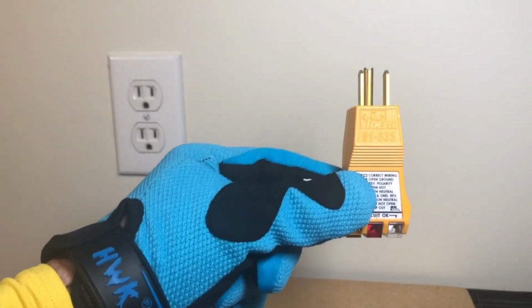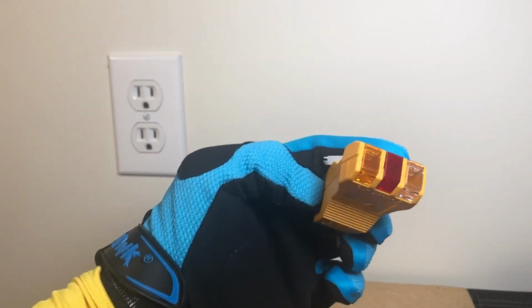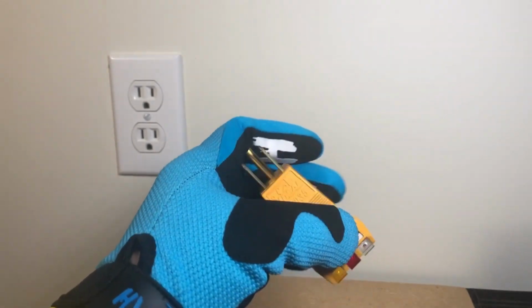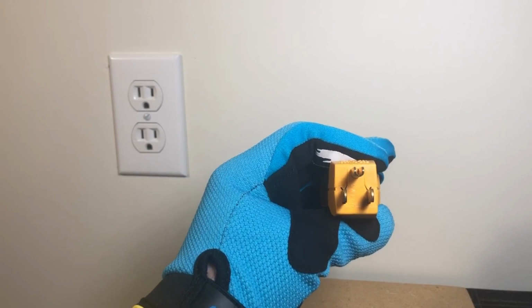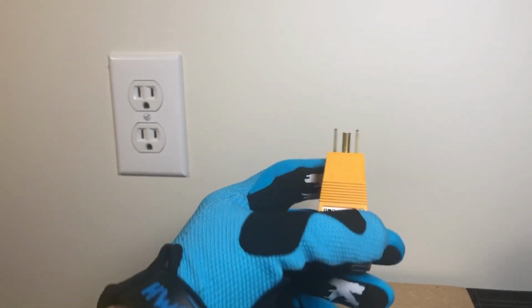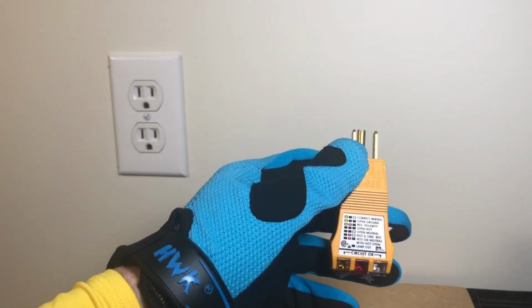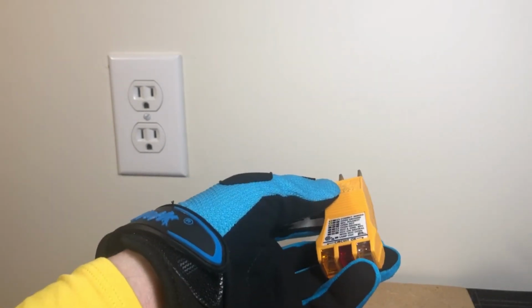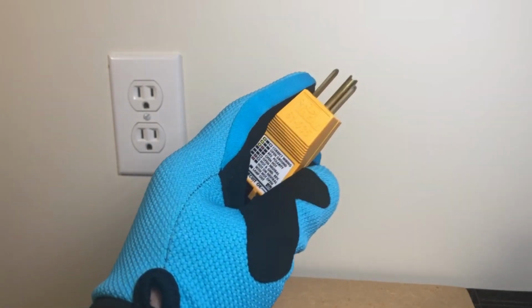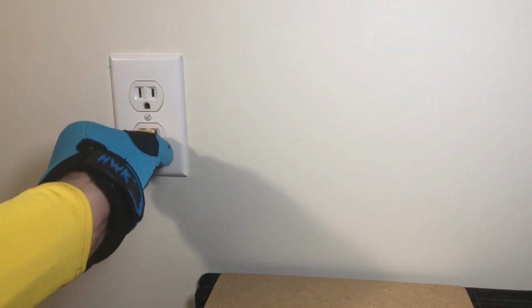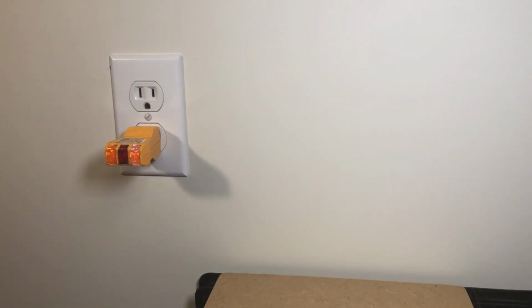Test number 2. This test does not require a multimeter, nor does it require an electrician. It is performed using a simple but effective device called a receptacle analyzer, also called an outlet tester. This 3-pronged device has one huge advantage over the multimeter. It analyzes the wiring of the outlet and indicates specific wiring problems with indicator lights on the device. And even better, it's simple to use. Plug it in and it tells the story.